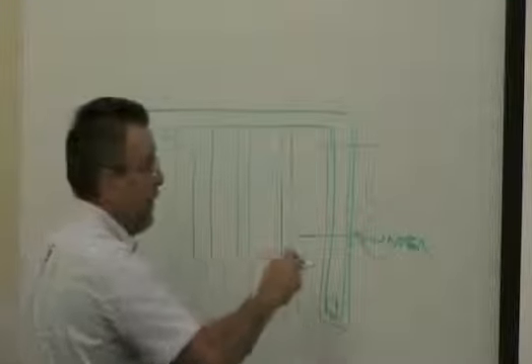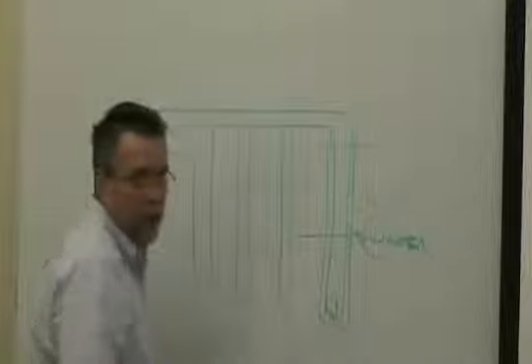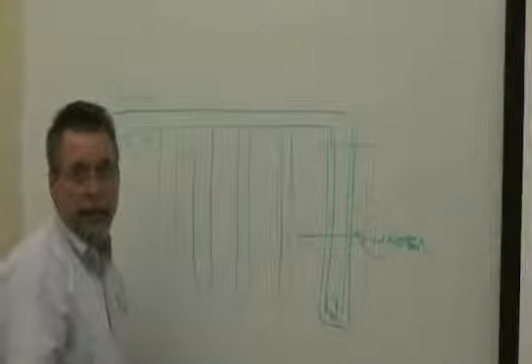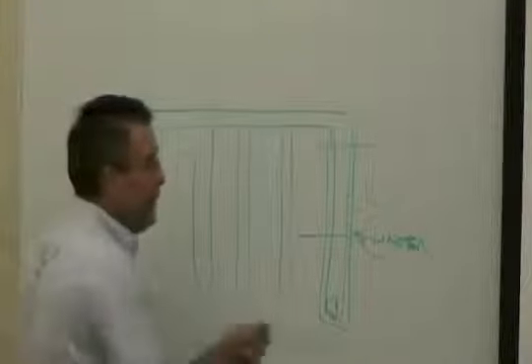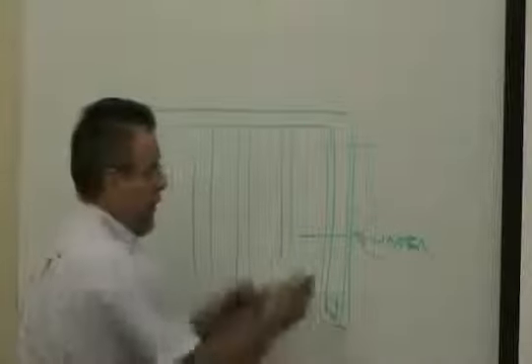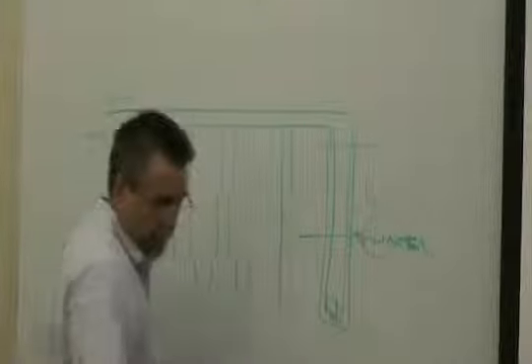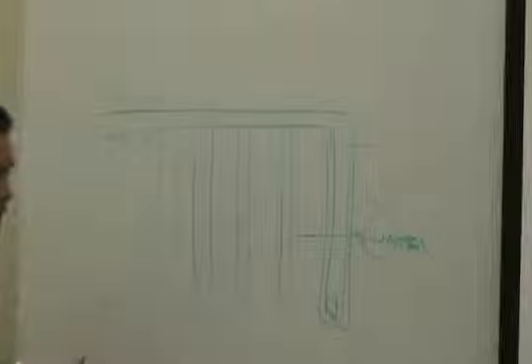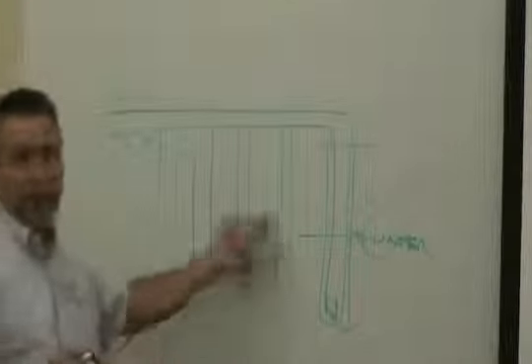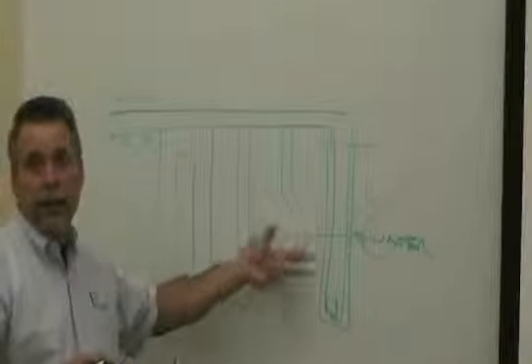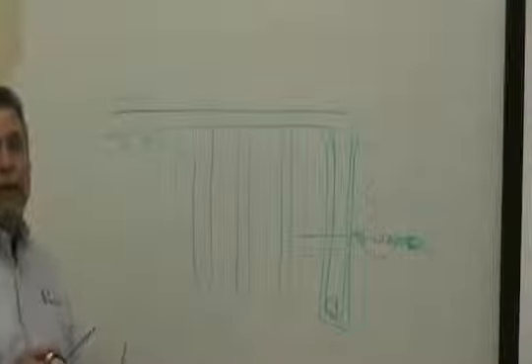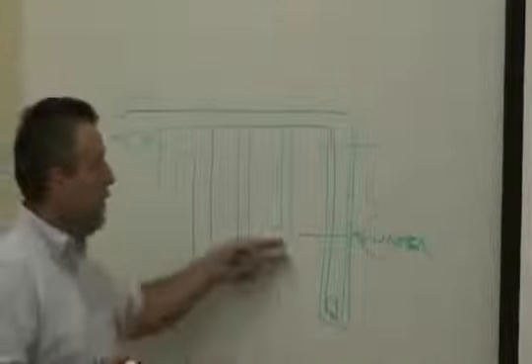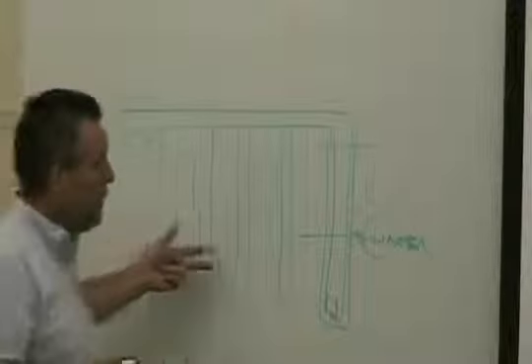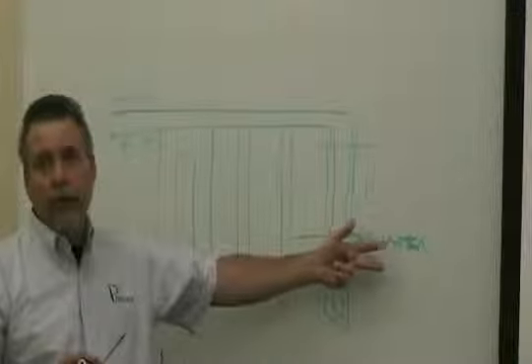If it's rock ground with water flow going through it, you have an incredibly good heat exchanger. If there's no water flow through the ground and it's purely sand or dirt, then there's really no heat exchange. I can't remember the terminology, but you're just heating the ground up, and eventually your loop goes bad. Pretty much like a dead air pipe then. Yeah. So ideally, you get high conductivity when you have water flowing through the ground.